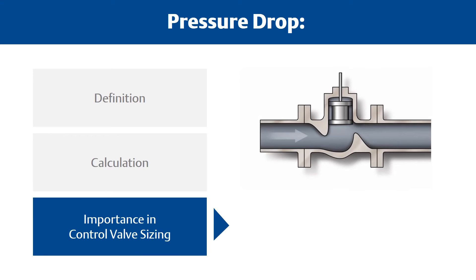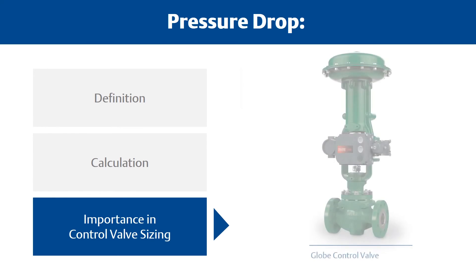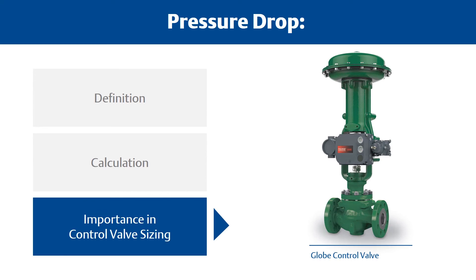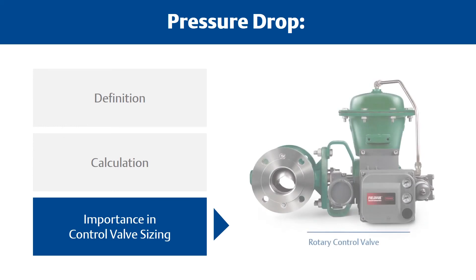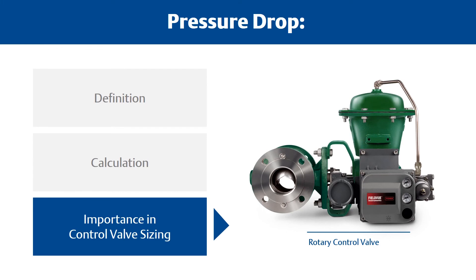The maximum pressure drop a control valve can tolerate at shutoff or when partially or fully open is an important selection criteria. Globe control valves are generally superior in both regards because of the rugged nature of their moving parts. Many rotary control valves are limited to pressure drops well below the body pressure rating, especially under flowing conditions, due to the stresses that high-velocity flow imposes on the disc or ball segment.